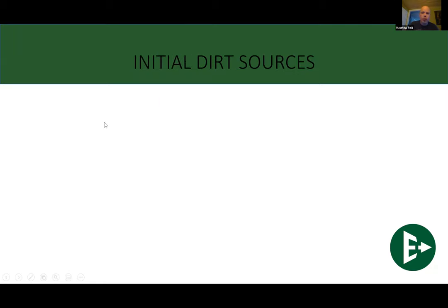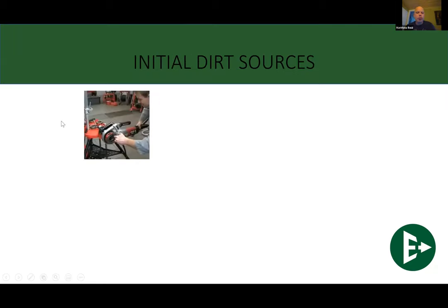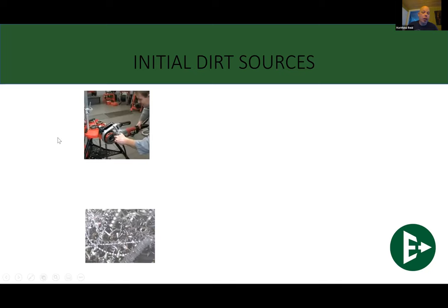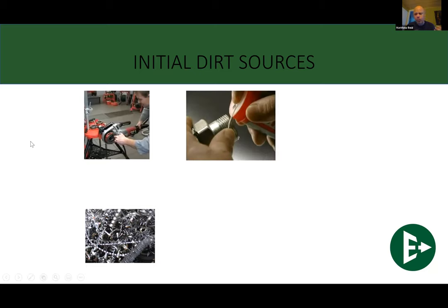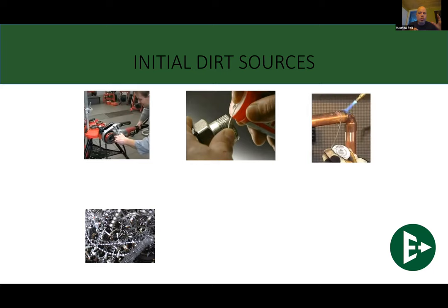So how do we do all this stuff? Let's talk about the initial dirt sources. How does dirt even get into a system in the first place? Well, if we're doing an iron pipe system, it's definitely going to get in from the threading of the pipe. You're going to see little metal filings on the pipes that you've just threaded, and it could be very, very small pieces, but they still get into the system and are classified as dirt. If you are using Teflon tape, dope, anything like that to ensure against leaks with your NPT connections, that absolutely can let go or chip off or flake off and create more dirt sources inside your hydronic system.